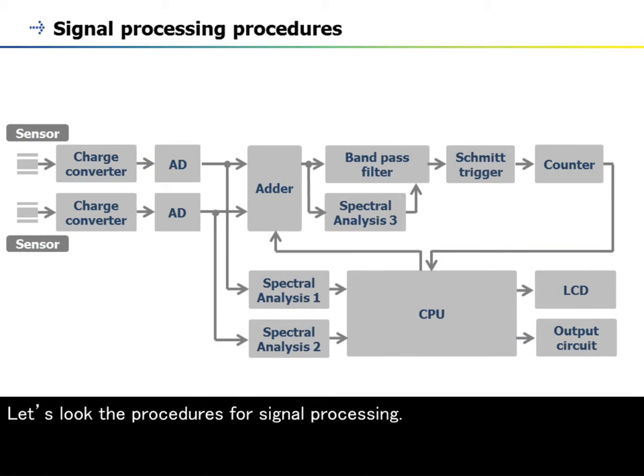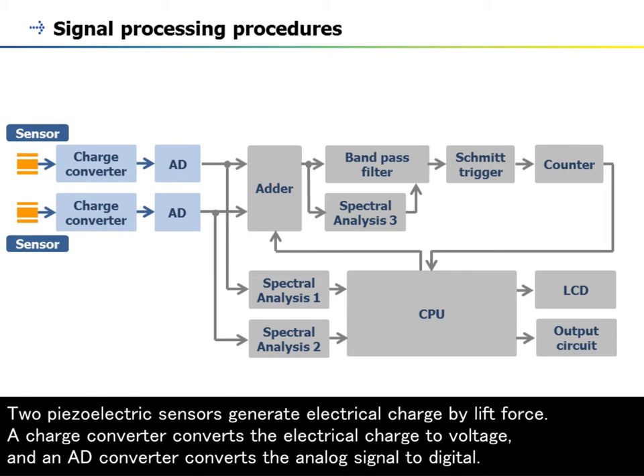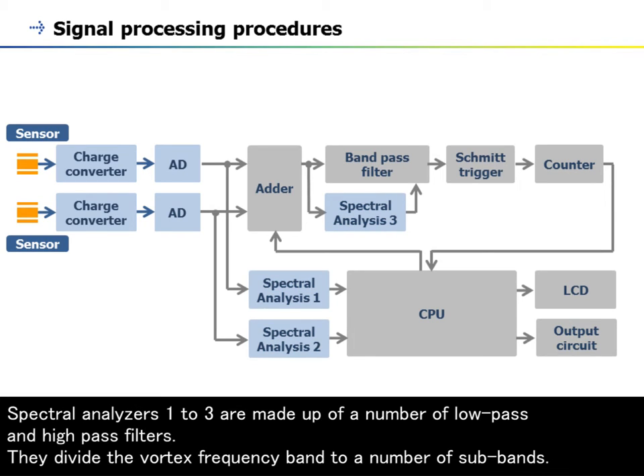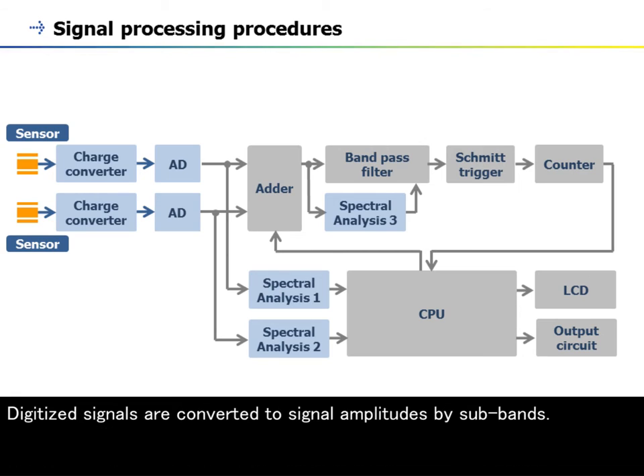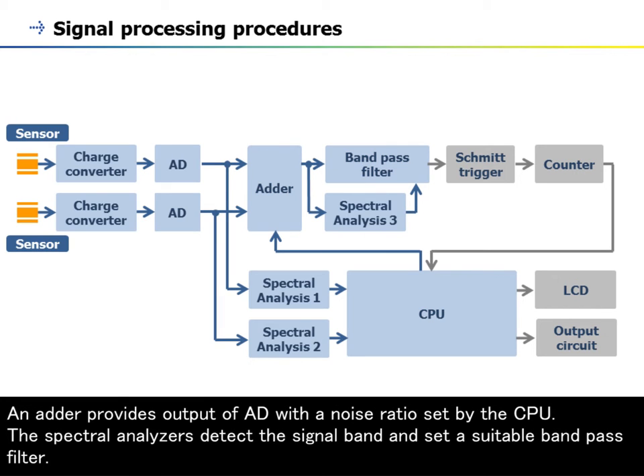Let's look at the procedures for signal processing. Two piezoelectric sensors generate electrical charge by lift force. A charge converter converts the electrical charge to voltage, and an AD converter converts the analog signal to digital. Spectral analyzers 1, 2, and 3 are made up of a number of low-pass and high-pass filters. They divide the vortex frequency band into a number of subbands. Digitized signals are converted to signal amplitudes by subbands. An adder provides output with a noise ratio set by the CPU. The spectral analyzers detect the signal band and set a suitable band-pass filter.